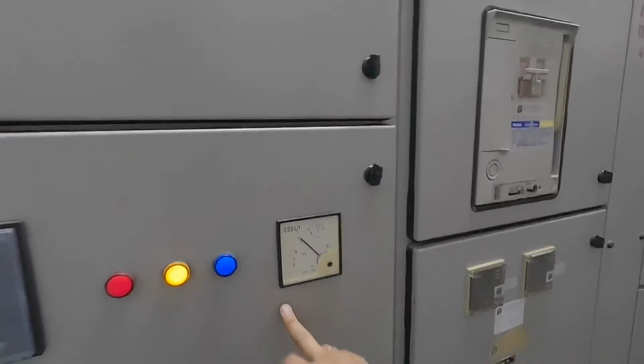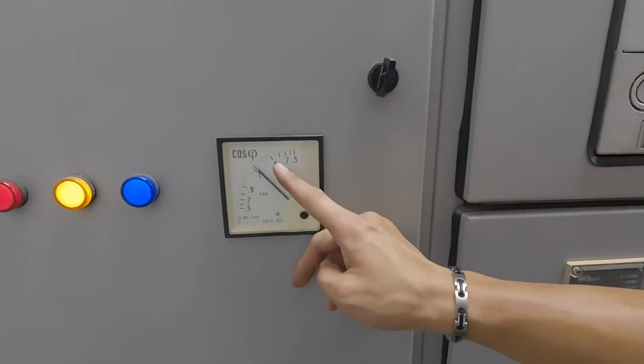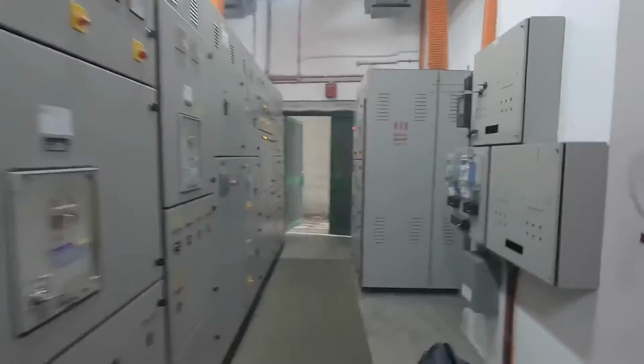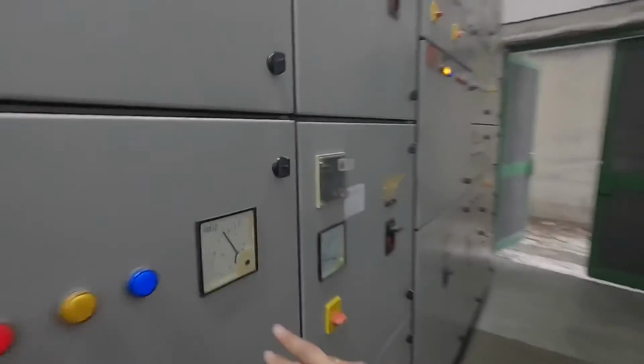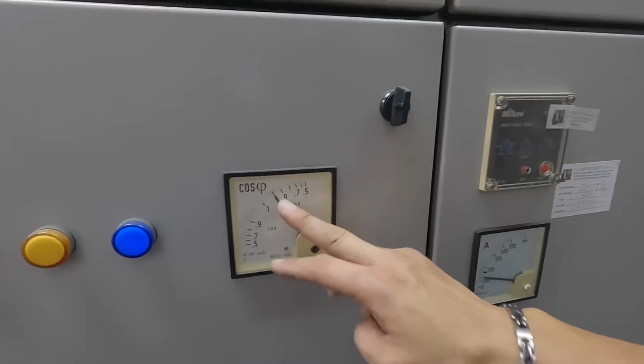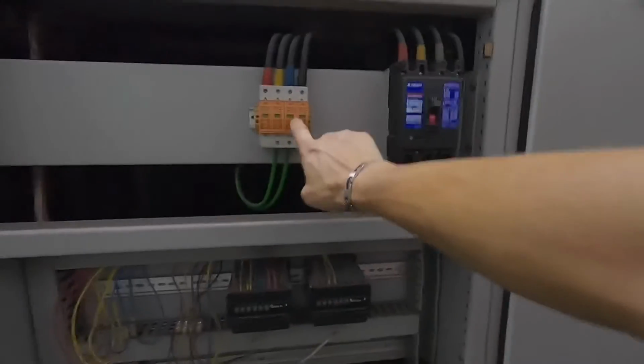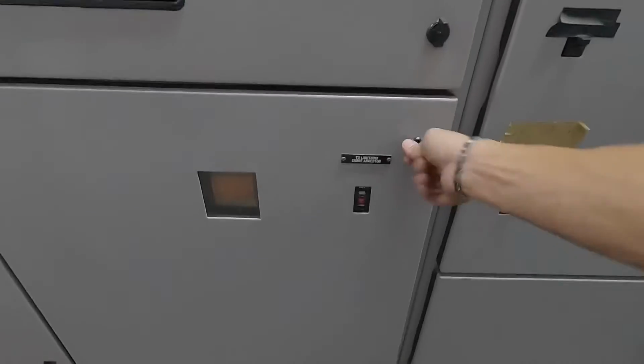Let it run by itself, let's just check some other things like the power factor. This is the MSB number 1 power factor. Currently the power factor is above 0.9. No step on. And for the MSB 2, power factor is at about 0.95. No step on. Both MSB panel surge arrestors are in good condition. This is the surge arrestor, as well as MSB number 2. Both surge arrestors are also in good condition.